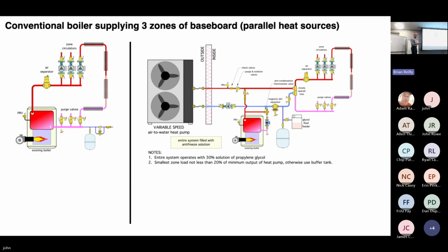But if you have what I call micro zones, what's a micro zone? A towel warmer in a bathroom has a separate zone. That might need 500 BTUs per hour. The heat pump simply can't go down to that capacity. So if you've got a lot of zoning going on, what I would do is replace this right here with a buffer tank. These 2 pipes would come in and out of the buffer tank. These 2 pipes would come in and out of the other side of the buffer tank. Now the buffer tank will provide the hydraulic separation for the circulators, but it also adds enough mass to the system so the heat pump isn't going to short cycle.